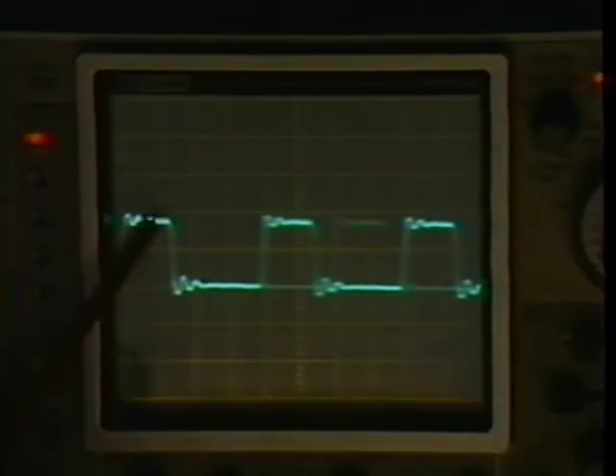Adjust the potentiometer for a 75 to 80 nanosecond pulse, measuring from the 50% level. Be careful not to unseat the extender board as you turn the pot. Next, check the D-run signal and make a coarse adjustment. Attach your scope probe to the D-run output of the WD-1100 and look for toggling. At this point, don't try to fine-tune the signal, just make sure that it is a pulse and not a DC level. This completes the preliminary adjustments.